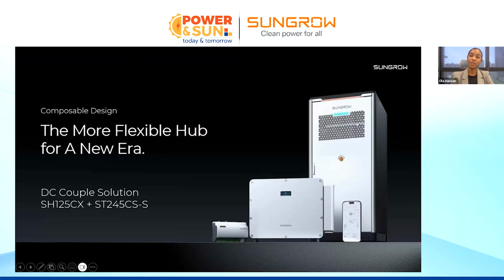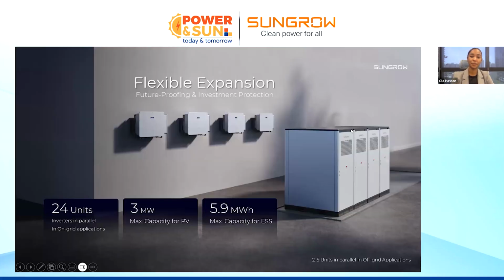So we have the ST245CS. In case of on-grid applications, we are able to install up to 24 units in parallel, giving us up to a 3 megawatt system. And each inverter can be connected to a 245 kilowatt hour battery system, giving us almost 5.9 megawatt hour.